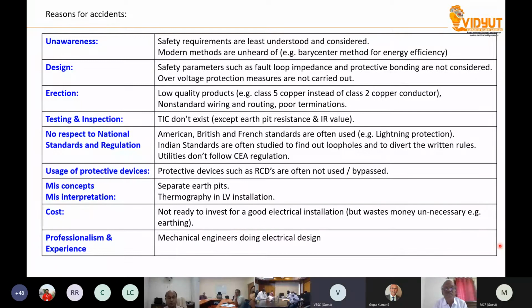And testing and inspection, except earth resistance and the IR value, strictly speaking, earth electrode resistance will not come into picture at all. For LV installation, unlike EHV and other things, earth electrode resistance doesn't come into picture because earth electrodes are provided to maintain a base between phase and neutral, and most of the fault current will be carried through the protective earthing conductor directly to the neutral. Only a leaking path will be available.